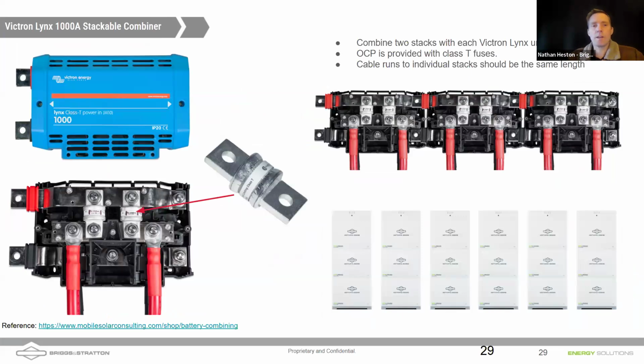You can have up to 10 different inputs coming into those DC combiner bus bars. Here's another example of a 1,000 amp combiner with fuses instead of breakers, a much cheaper option. I've got 2 of these here in my shop set up with 4 of those Class T fuses. I ended up using 250 amp Class T fuses, so you can bring up to 4 stacks of batteries in with 2 of those devices, 6 stacks total. Each device lets you bring in 2 more stacks, and they're stackable devices. On the right side of the screen, you can see we've stacked them one on top of the next.